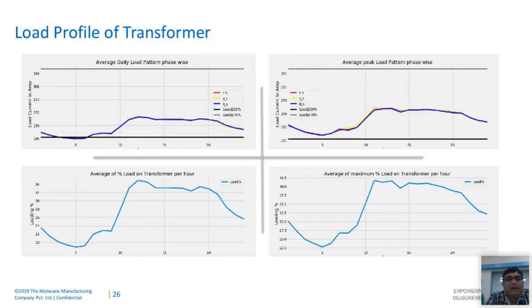So one of the very important parameters is the loading of the transformer. Since we are capturing the data in real time, we can do a lot of load profiling, where the average daily load pattern phase wise is plotted. The peak load, the average peak load in a particular month or period, can also be plotted. This essentially gives a good idea about how the transformer is getting loaded at different periods or at different seasons. We also plot the percentage loading of the transformer per hour, or the average percentage loading.